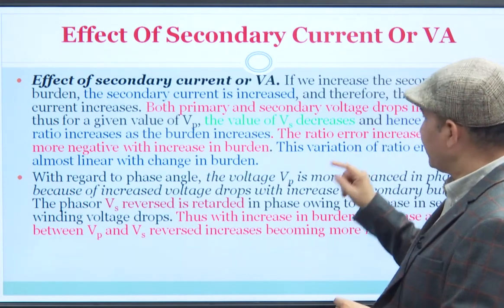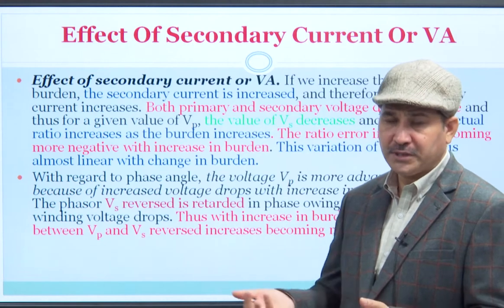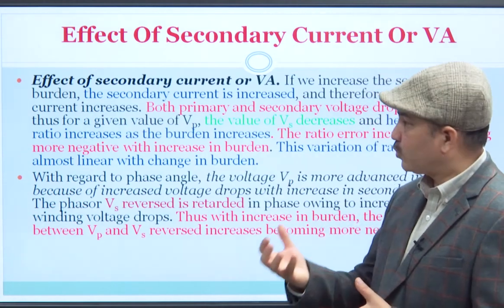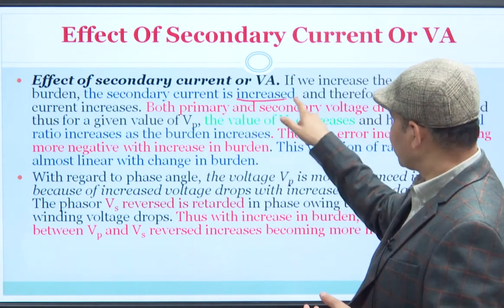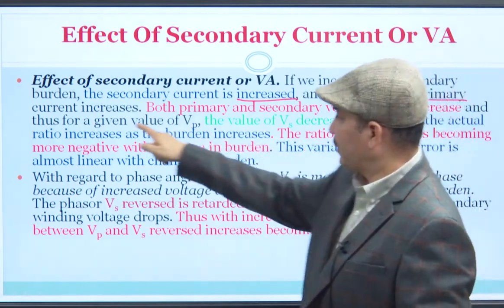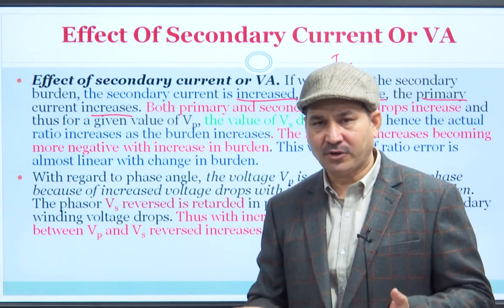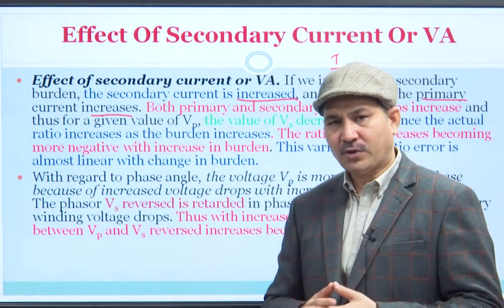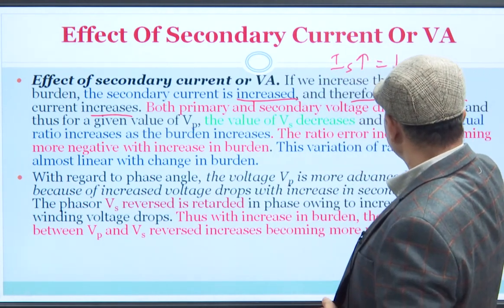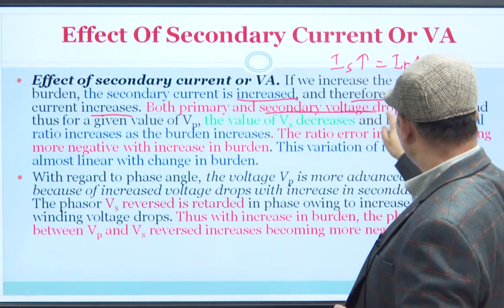Let us first start with the effect of secondary current or volt-ampere. If we increase the secondary burden — the burden connected to the potential transformer, which may be a voltmeter, relay circuit, or voltage coil of a wattmeter — then if you increase the load, the secondary current will obviously increase. And if the secondary current increases, then the primary current will also increase. Because if Is is increasing, you have to draw more power from the primary — so Ip also needs to increase. Therefore, both primary and secondary voltage drops increase.